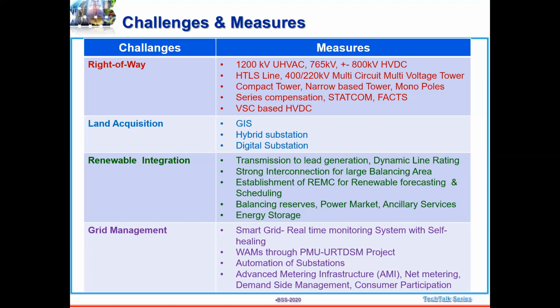Dynamic line rating depends on ambient conditions. We measure these conditions and predict the actual loading the line can take based on system conditions like sag, solar radiation, wind speed, and ambient temperature, along with conductor temperature. With real-time monitoring already implemented in a project, we have seen around 20 to 30% more loading possible on the same line when DLR is used.